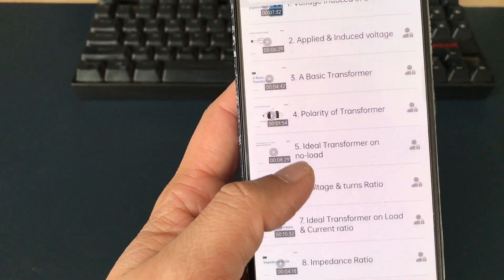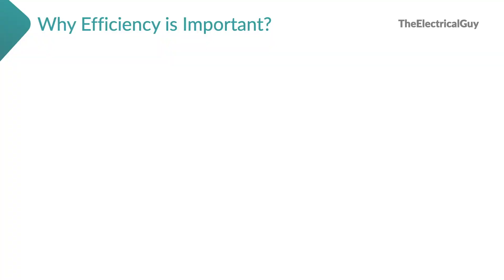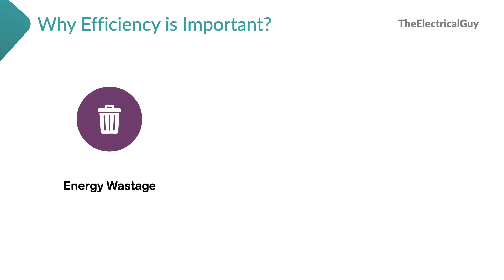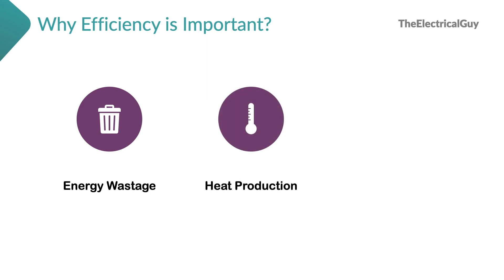Let's talk about why efficiency is important and what are the effects of low efficiency. For understanding purpose, let's stick to the motor example, but you can connect this to any other electrical devices. Poor efficiency means the motor is generating more non-useful energy than useful energy — the input energy is getting wasted in producing non-useful output. Non-useful output, the majority of the time, means production of heat. As efficiency decreases, heat increases, which causes a significant increase in temperature of the device. High temperature is one of the biggest concerns in developing reliable electrical or electronic devices.